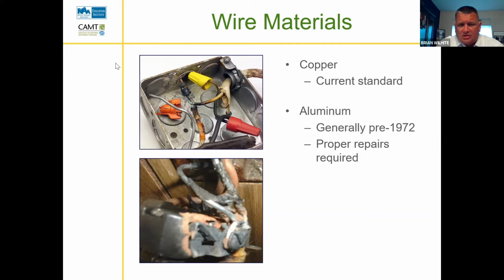Now, what is the problem with our top left picture? They got the ground wire capped off. Say that again. It looks like they have the ground wire capped off. What else? Those things blew up. Say that again. There's an arc fault. Yeah, so when we connect aluminum to copper, since that aluminum, as we run electricity through it, gets heated and it becomes soft, and the connections become loosened and they start to arc. And that's what's happened here. There's not a tight connection, so between the two of them, it starts to arc.